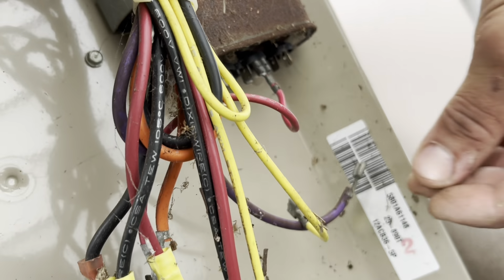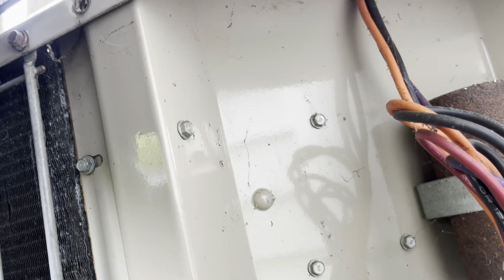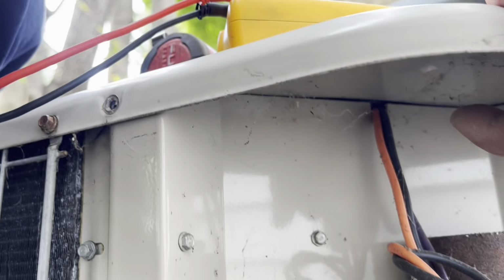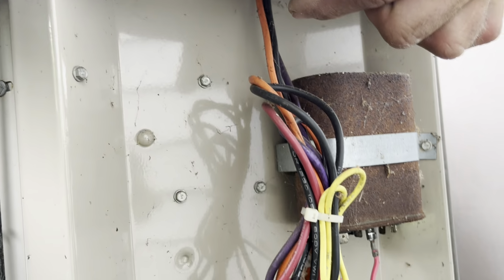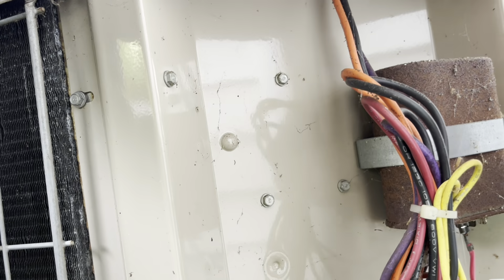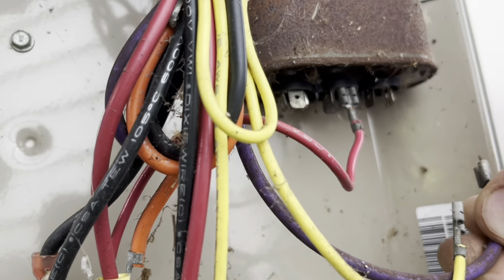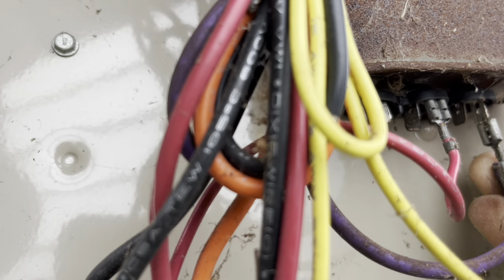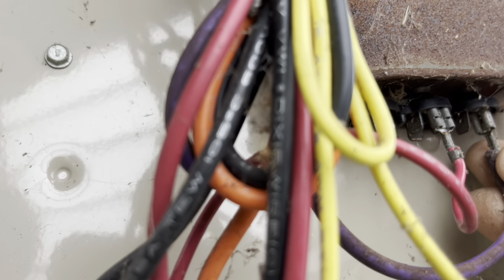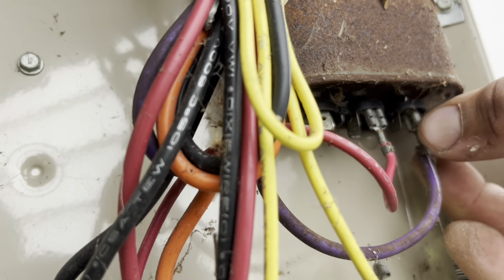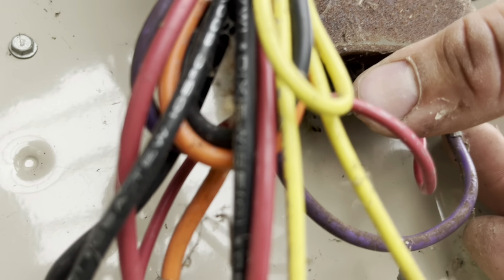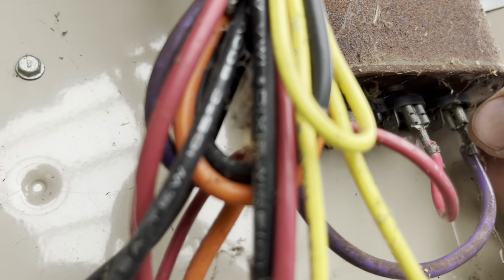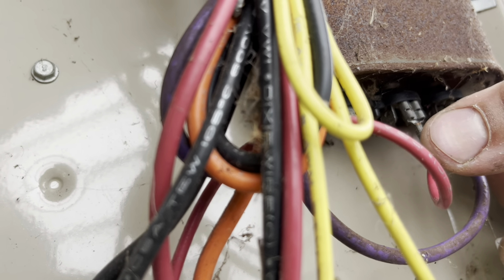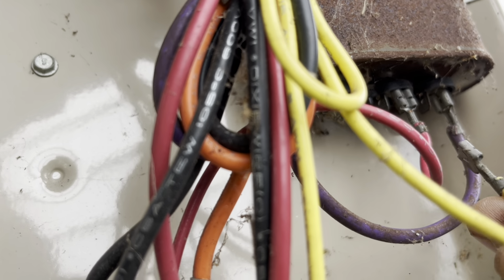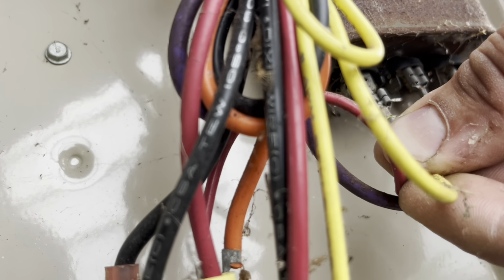It's in the middle on this one. Okay, then I can see that my purple wire is coming from my fan here. This wire is coming down, we're gonna put this to fan. And the fan - we don't always know, but like Mikey Pipe says, you have 2 prongs, 4 prongs, 3 prongs. So usually your 3 prong is your Herm, your 2 prong would be your fan, and your 4 would be your common. That's not always the case, but most of the time it is.